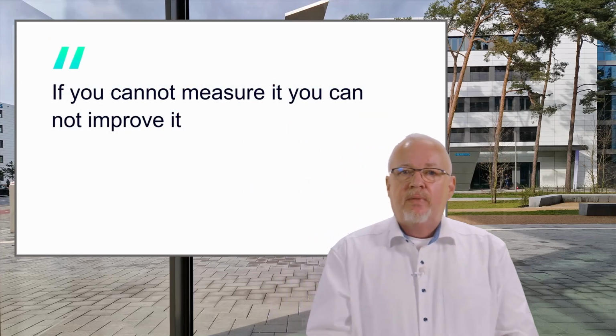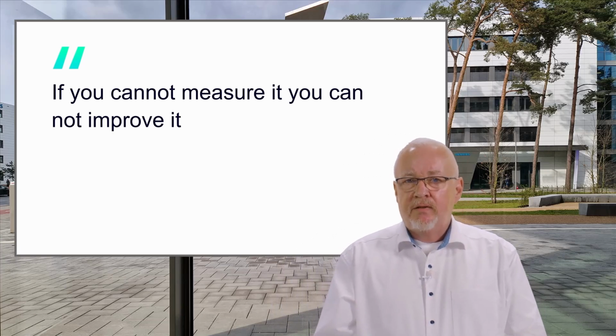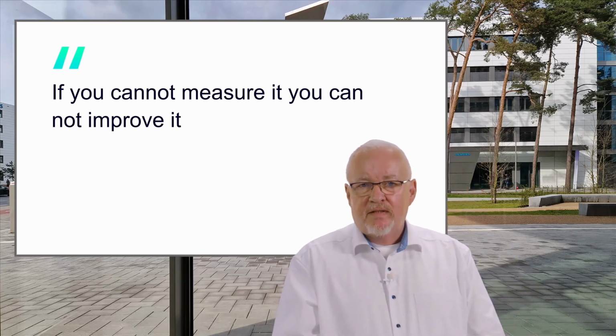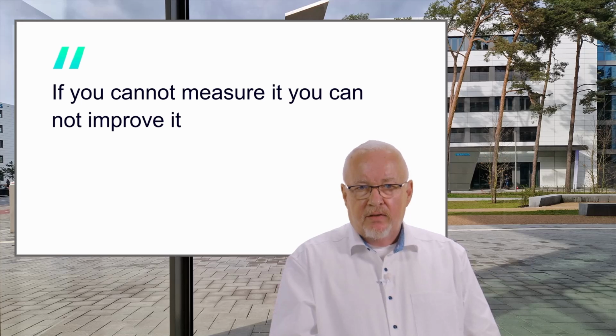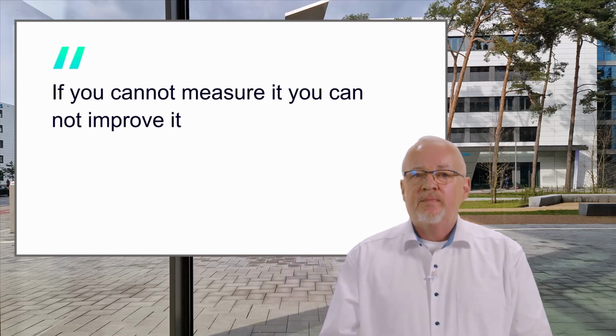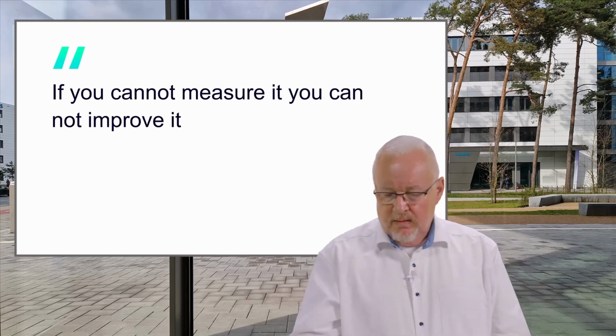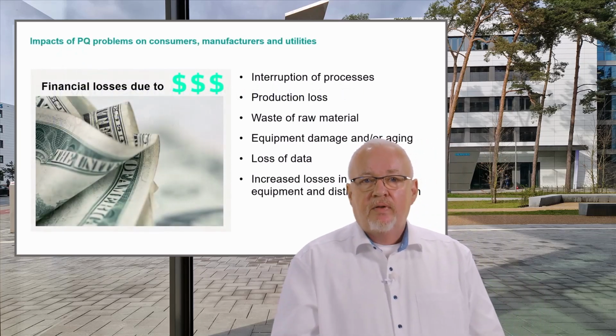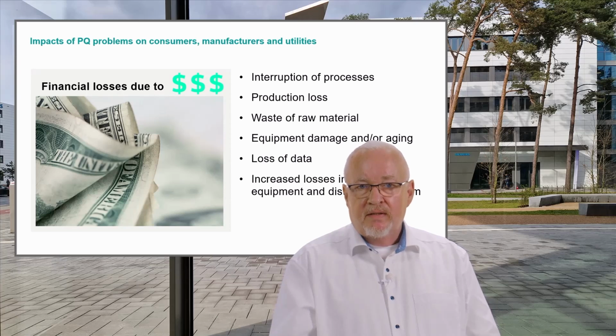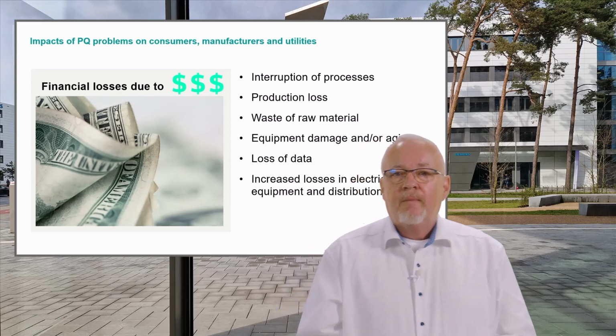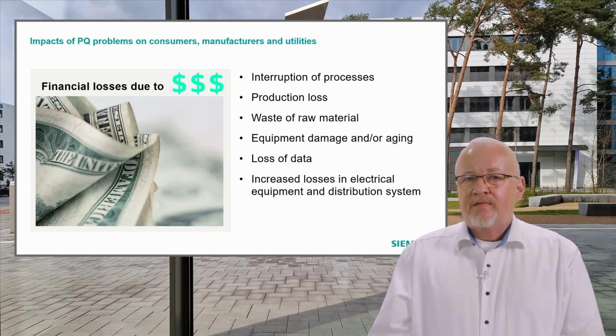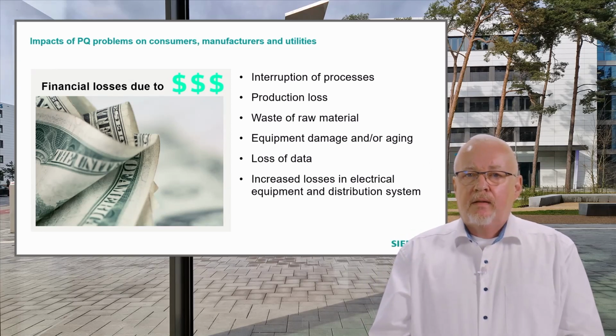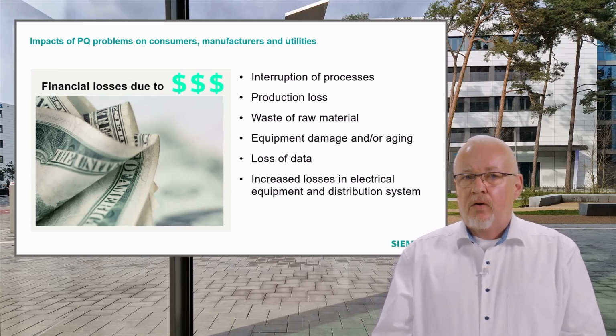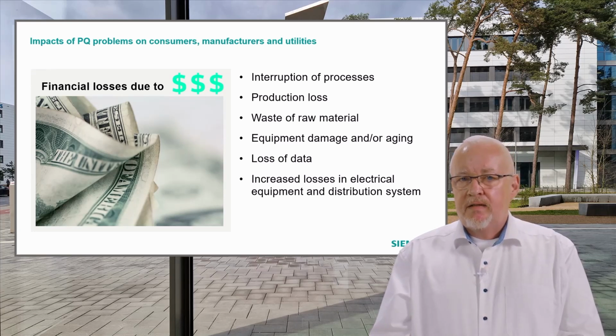The main motivation for power quality monitoring is: if you cannot measure it, you cannot improve it. The power system is changing rapidly. To adjust to ever-present changes in the system, continuous measurement should be preferred over spot measurements just in case of problems. What are the impacts of bad power quality on consumers, manufacturers, and utilities? Always financial losses due to interruption of processes, production loss, waste of raw material, equipment damage or aging, loss of data, or increased losses in electrical equipment and distribution systems.